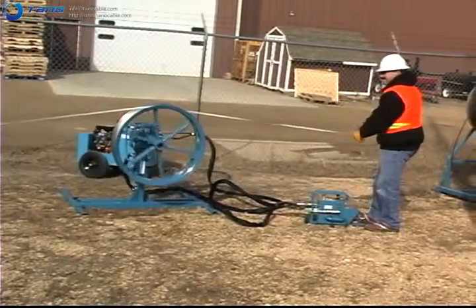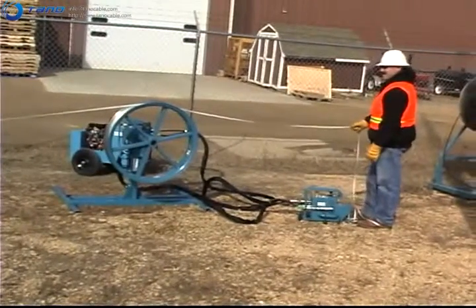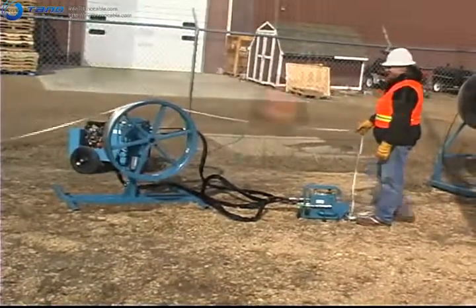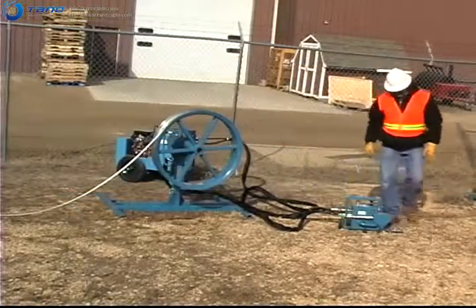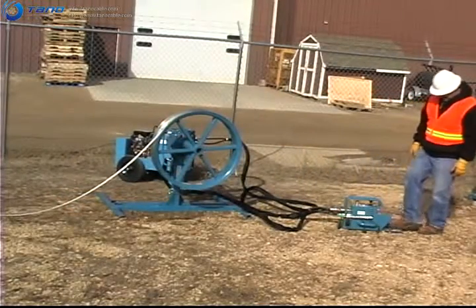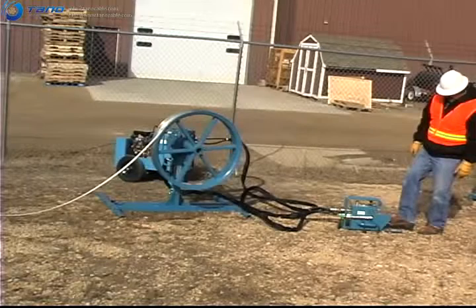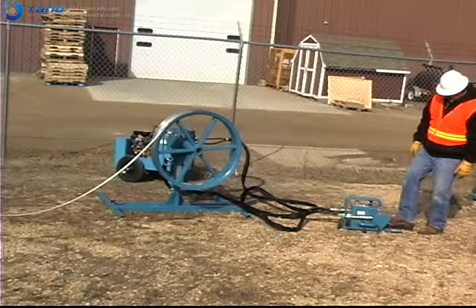Release the foot pedal and the cable or pull line tension will slowly release. Slowly reverse the puller to release cable or pull line tension by lifting up on the foot pedal. Many pull lines build up tension from stretching. Never approach or service a pull line under tension. Always release tension before proceeding.